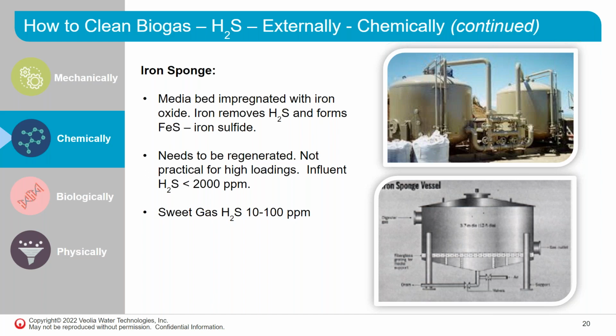Iron sponge. This is actually another unit that we can use to chemically remove or chemically clean your biogas by removing hydrogen sulfide. It's a relatively cheap and widely used method to remove hydrogen sulfide if the hydrogen sulfide loading is low. So basically these systems are filled with media impregnated with iron oxide, and usually the media is some sort of wood chips. And as biogas flows through these vessels, the H2S reacts with ferric oxide and forms ferrous sulfide.